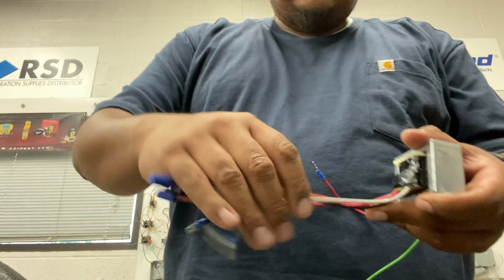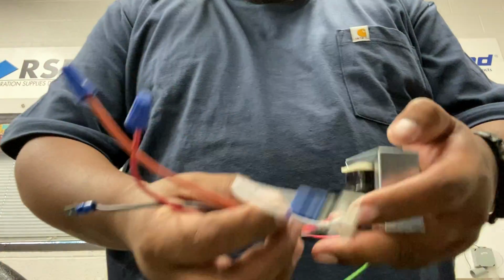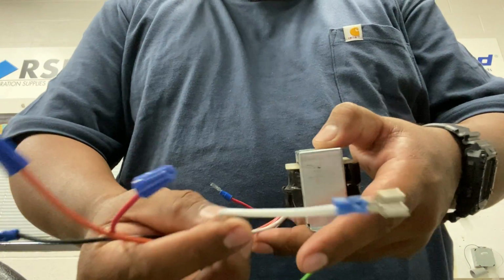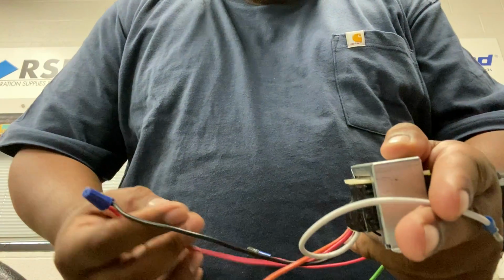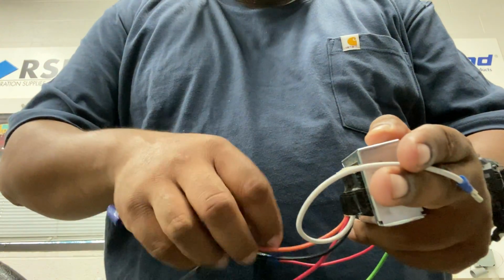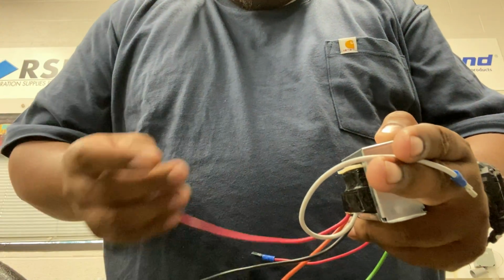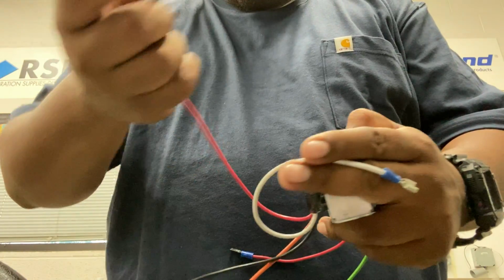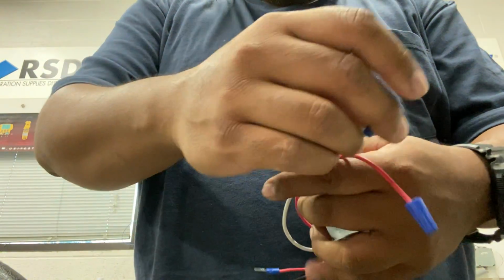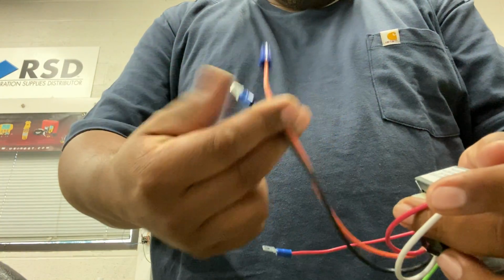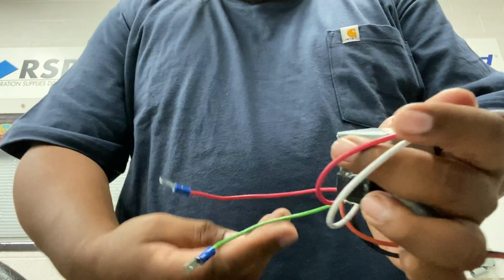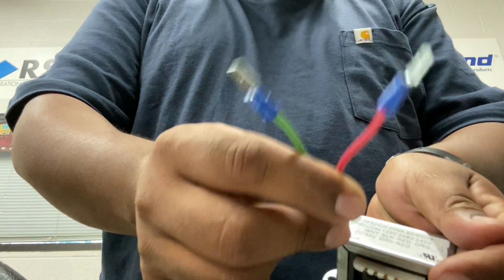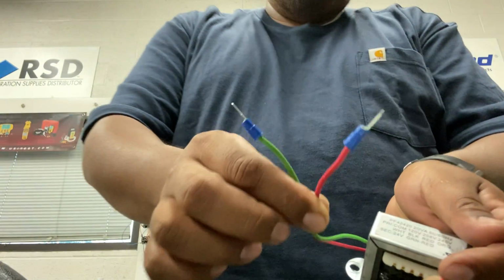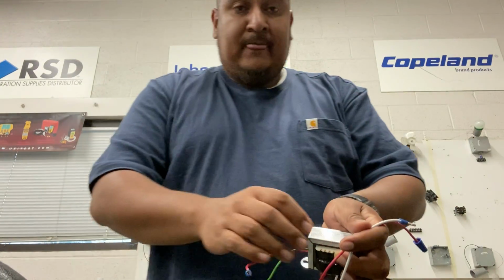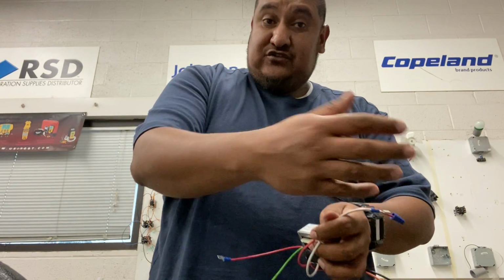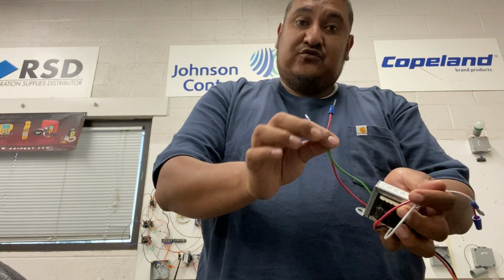So just like it says, if we're operating on 208 volts, we're going to look at the top of this transformer here in white. It's going to be our common, so we'll leave that here. And then we'll go with red. So we're going to hook up 208 volts to these two lines here. These lines here will get capped off and moved to the side. And then coming out of these two, red and green, this is where our 24 volts is going to be coming out. So we're taking high voltage, 208 volts, coming in through here, and transforming it to 24 volts.